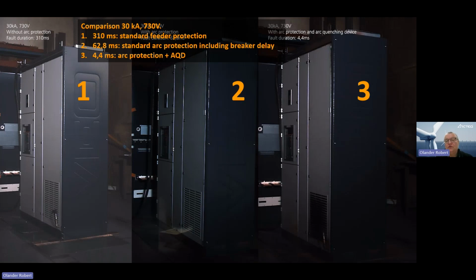So now you will see how it reacts. So this is in slow motion, of course. So you can see that in number 3 you see a small flash. In number 2 you see a bigger flash. But still here, even though you had that big flash, it was okay to go. It did not destroy the bus bar of the device. So it was still okay. But then you see number 1, it's just going on, and it's destroying the switchgear fully, and also it's very dangerous for people. And here we are talking about 30 kiloampere. It's low voltage, so it's 730 volts in this one. So it's a low voltage switchgear in this case.